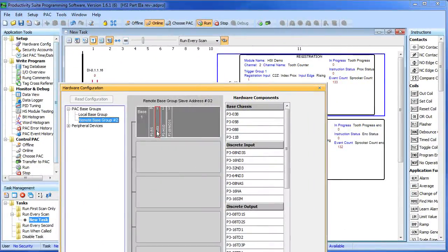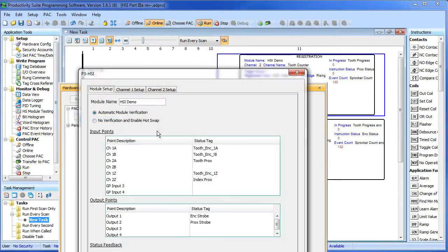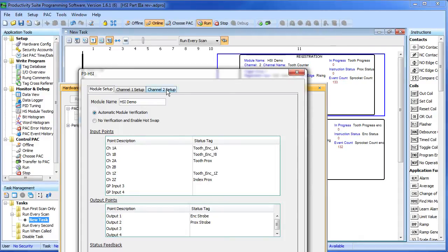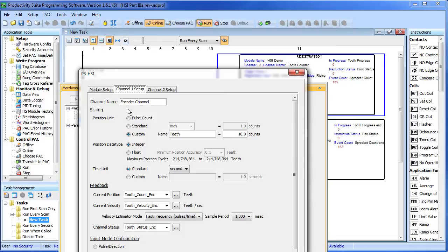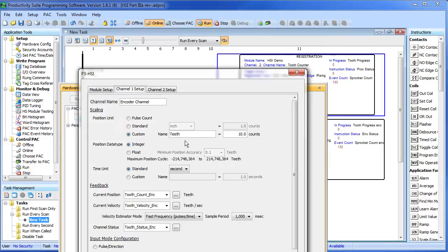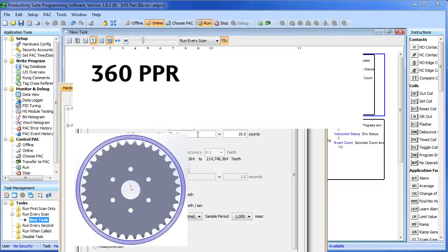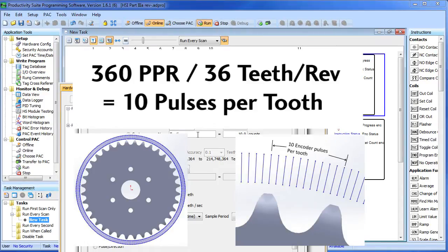Here's the hardware configuration of the HSI module. We've added the encoder inputs on channels 1A, 1B and 1Z. We still have our PROX sensors set up on channel 2 and I simply copied most of those settings over here to channel 1. We'll name this the encoder channel and we'll use our custom units again. But here's the trick. Since everything we did in the previous video is in custom units of teeth, all we have to do here is modify the number of counts that give me 1 tooth.